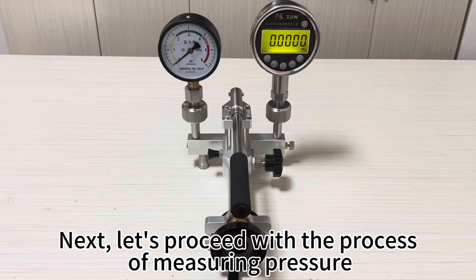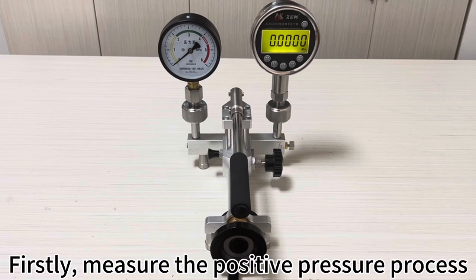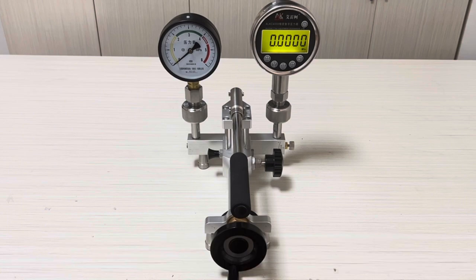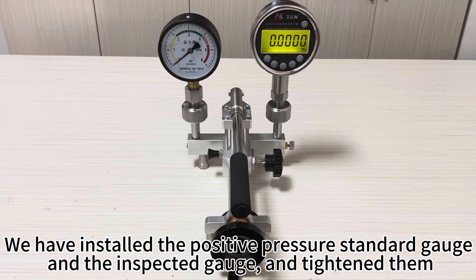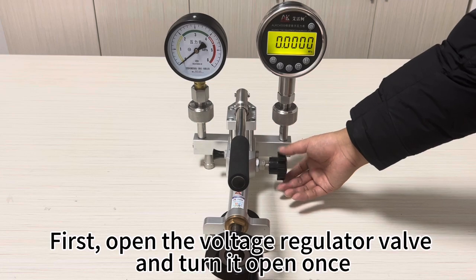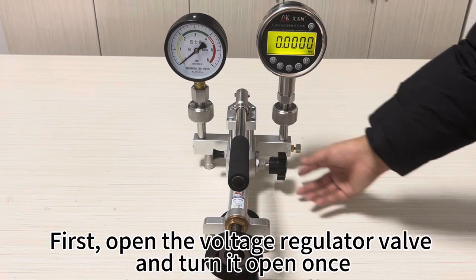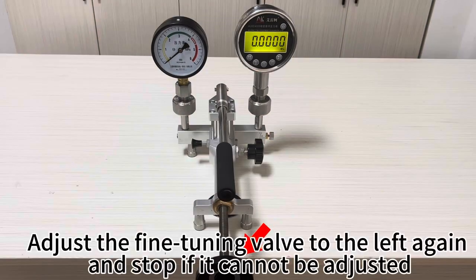Next, let's proceed with the process of measuring pressure. Firstly, the positive pressure process. We have installed the positive pressure standard gauge and the inspected gauge and tightened them. First, open the shut-off valve and turn it open once. Adjust the fine-tuning valve to the left and stop when it cannot be adjusted further.